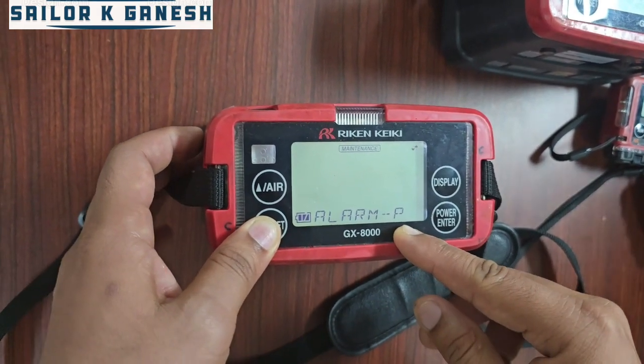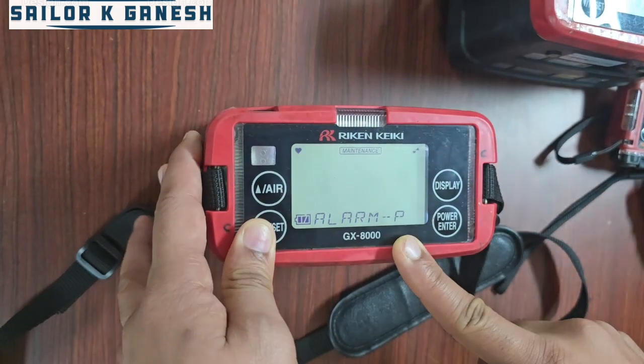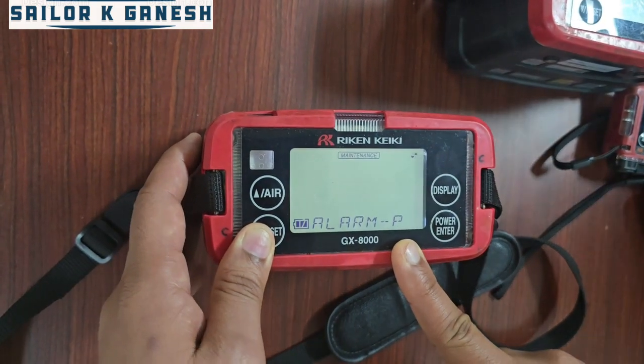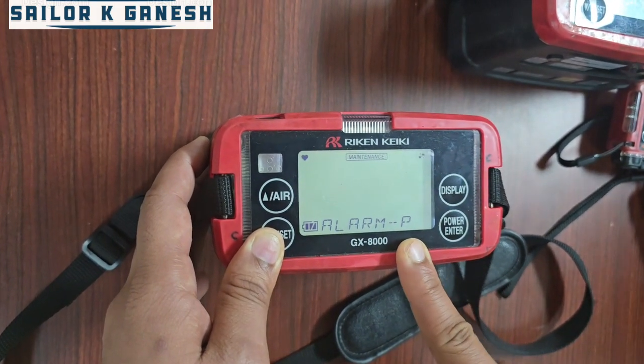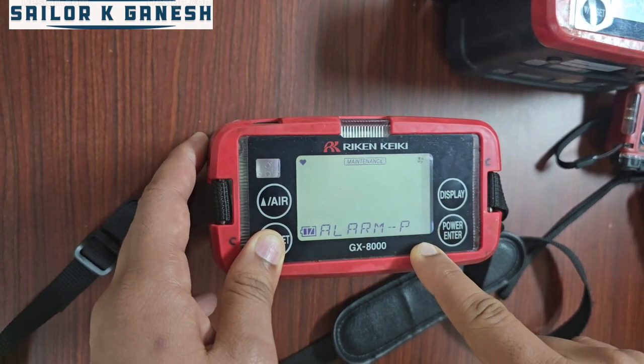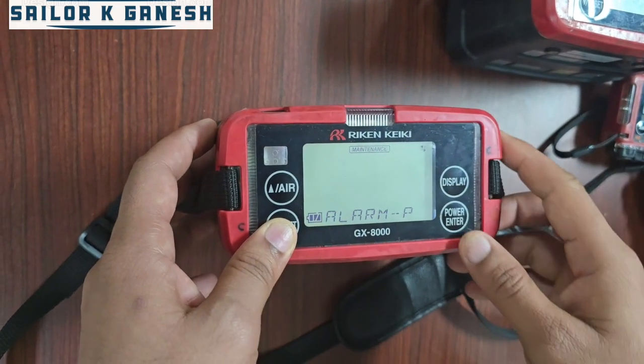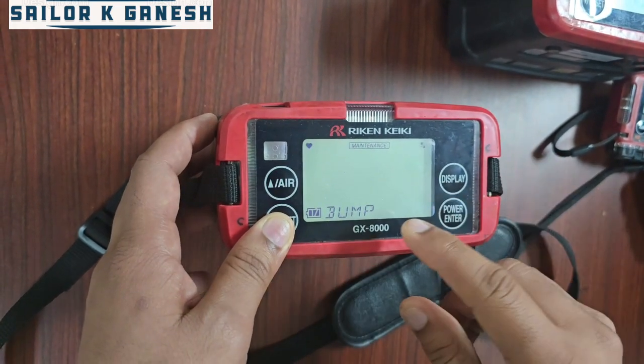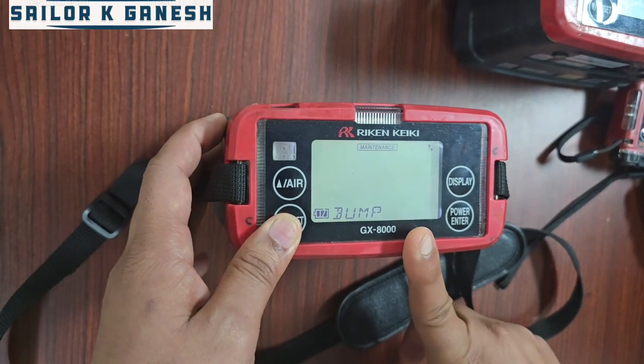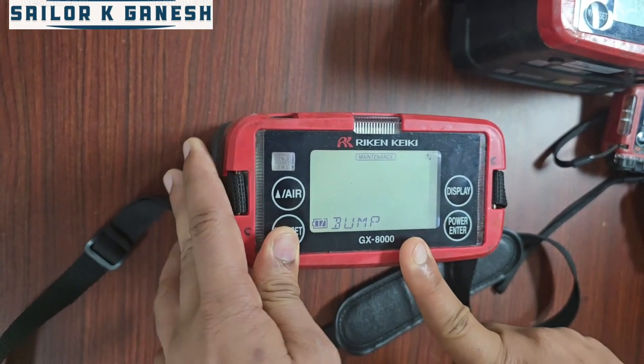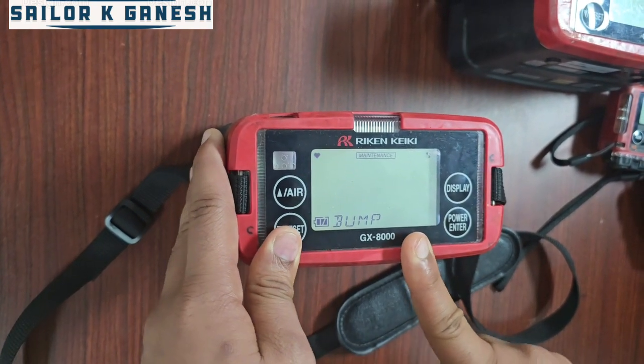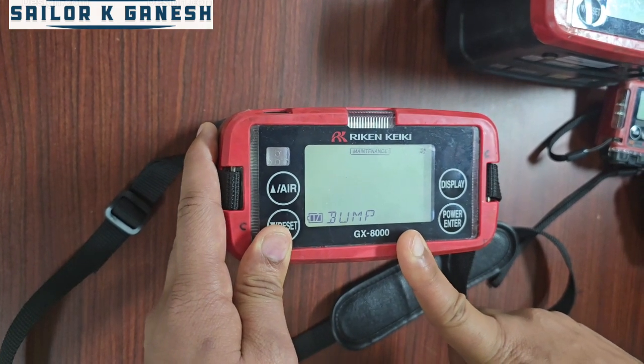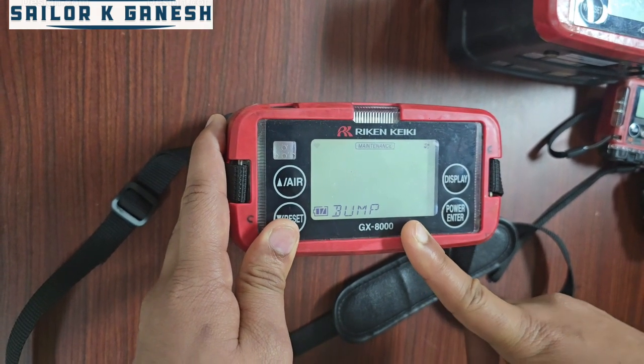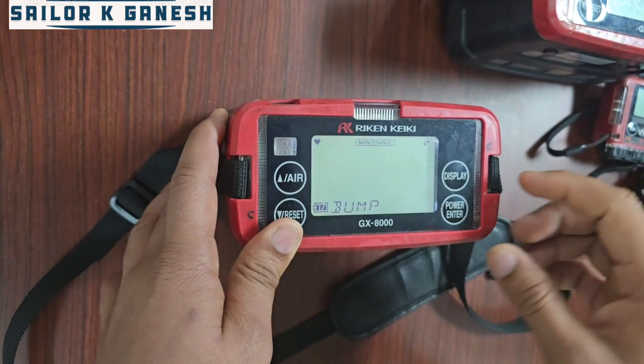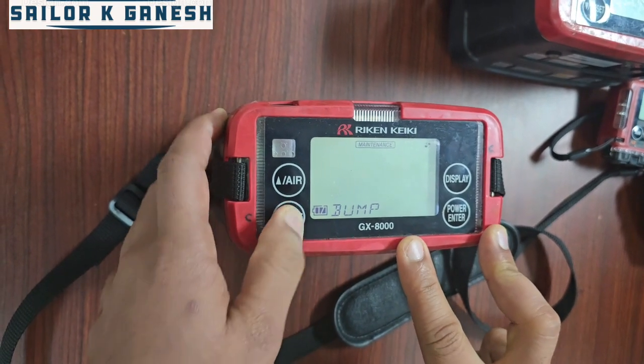This is another requirement: to set the alarm for when you are going to the tanks. You're supposed to receive any kind of alarm. So here we can set the alarms as per our company manual. The next is bump. This is a bump test. This test is generally required because every time you cannot calibrate the equipment. So when you are going for frequent rounds in the tanks, at that time with your span gas bottles, you can do the simulation test. That is called the bump test.